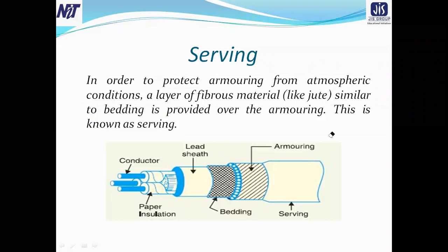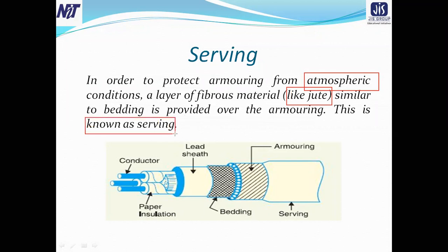The last cover of the cable is the serving. In order to protect the armoring from atmospheric conditions, a layer of fibrous material like jute is provided over the armoring. This is known as serving. So the external part of the cable is called the serving, and it also serves a protection purpose, similar to bedding, using fibrous material like jute.